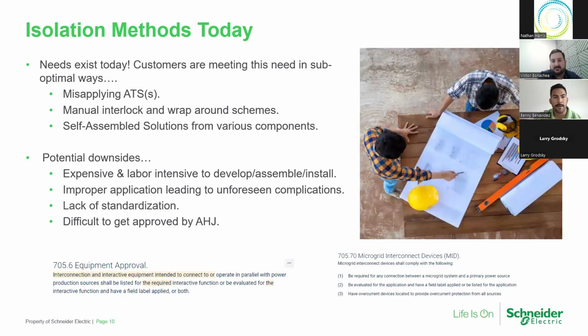Good clarification there, Victor. Okay, so isolation methods today, servicing customers. We've seen a couple of single line diagrams where they're misapplying automatic transfer switches. They're using ATSs to create isolation where they're only connected to one power source, leaving the second power source just idle with no power connections. There are also manual interlock schemes, see manual transfer switches or Kirk key interlock schemes, to create this isolation. And there are self-assembled solutions where we've seen contactors and relays installed, basically assembling these solutions on site, putting a lot of stress on the contractor. The downside of these isolation methods is that they're going to be labor intensive, especially if it's the first time someone's installing one of these microgrid systems or interacting with the energy storage system.